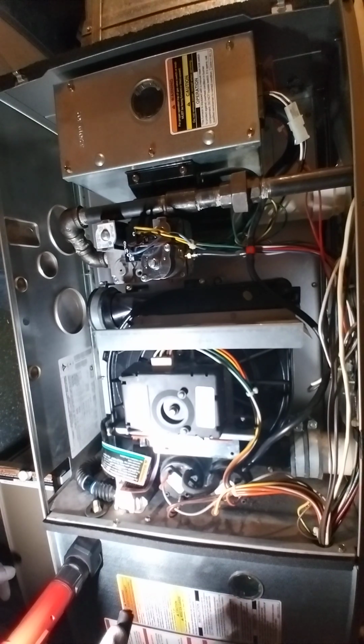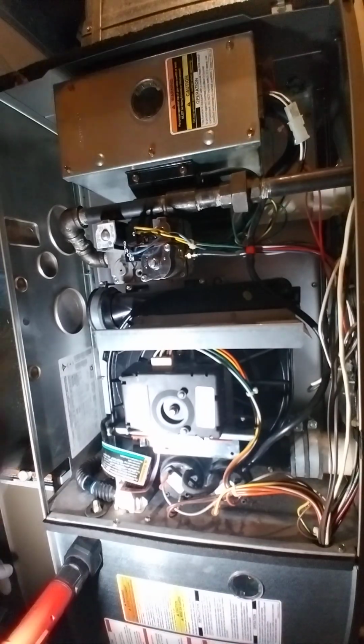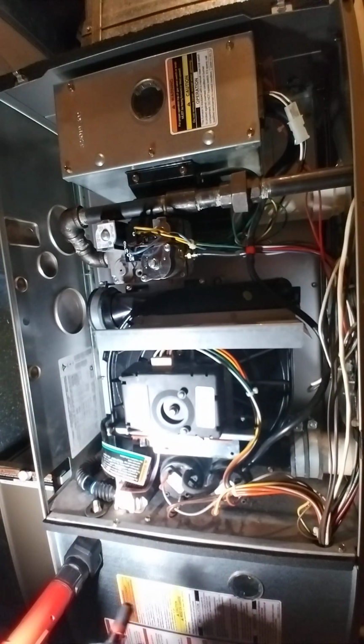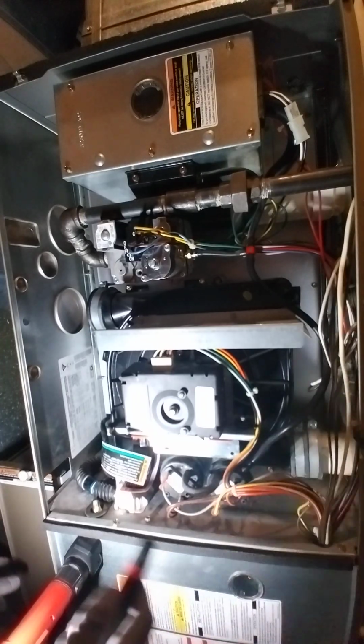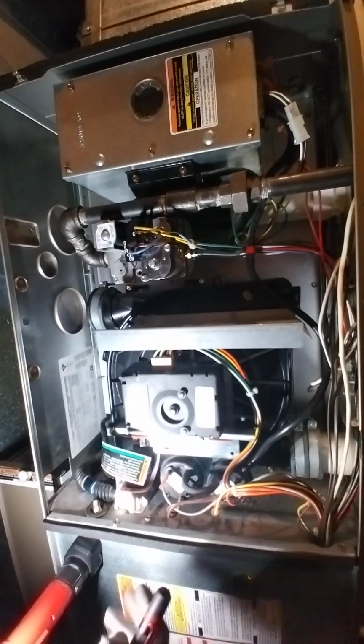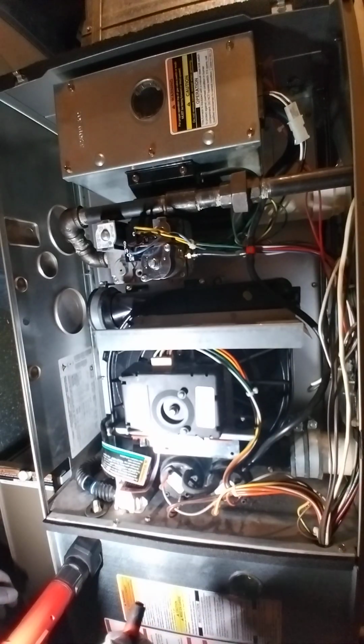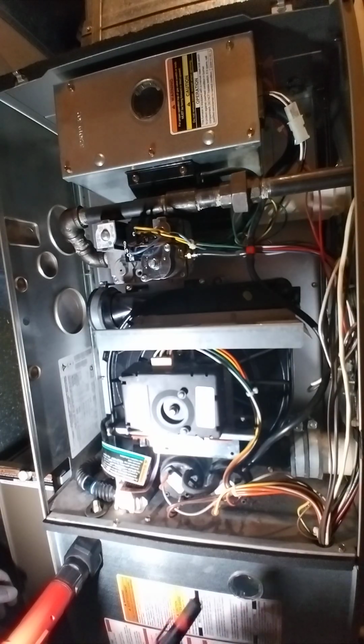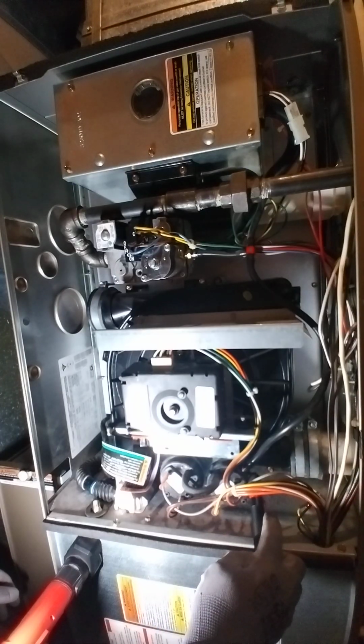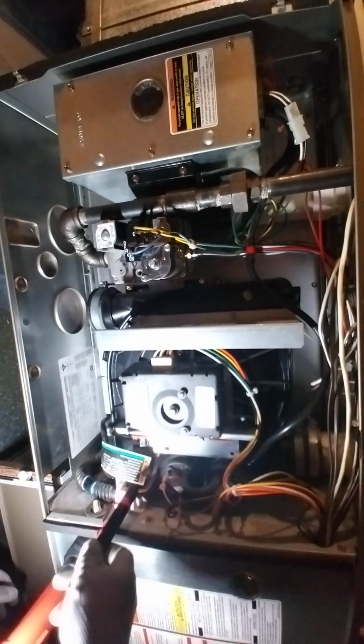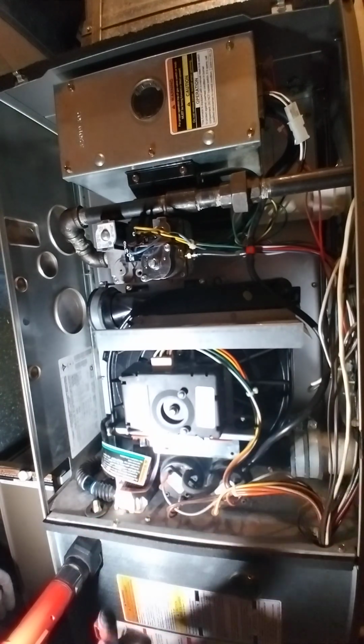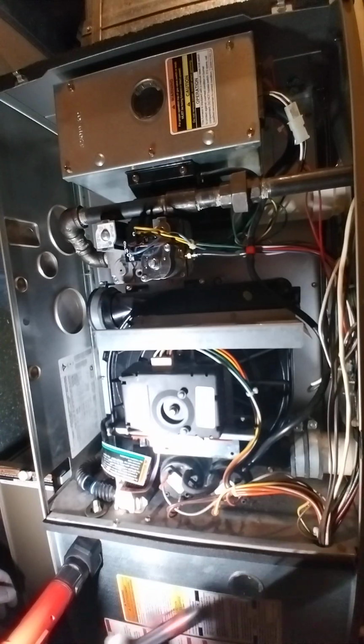So I started looking through the manual as well. It wasn't that. No overtemp sensors, clearly no overtemp problems based on the thermocouple readings I was getting. So that's when I started checking the pressure sensors, because you could hear them clicking during the normal cycling of things. So I started watching those sensors, and that's when I found that the low pressure switch right here was cutting out. Strangely enough, the high pressure sensor wasn't having this issue.